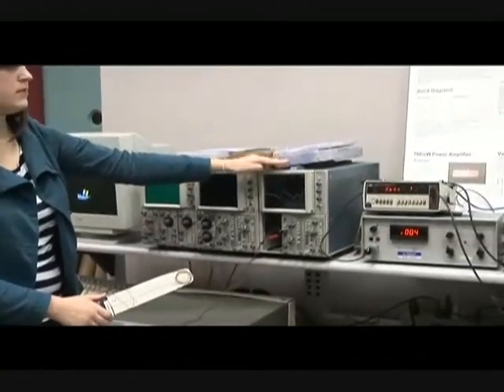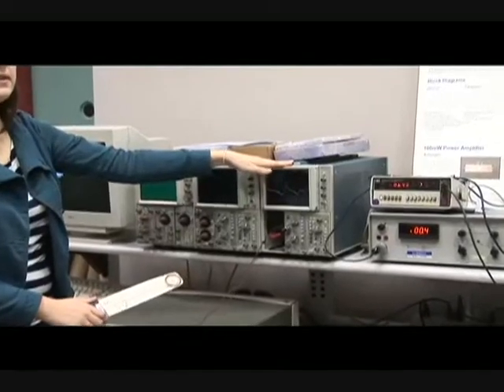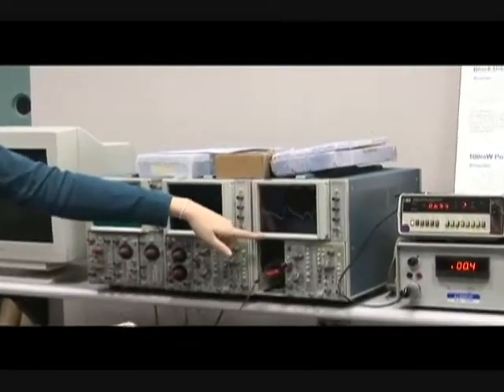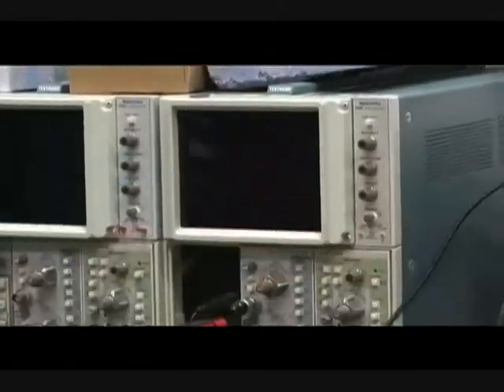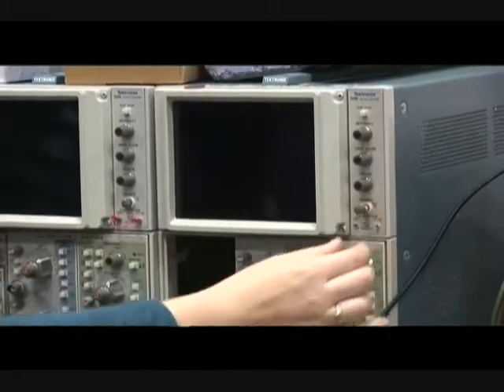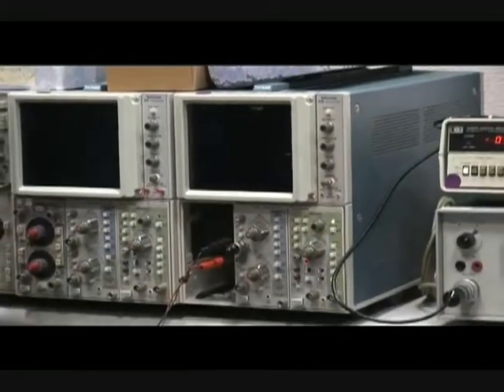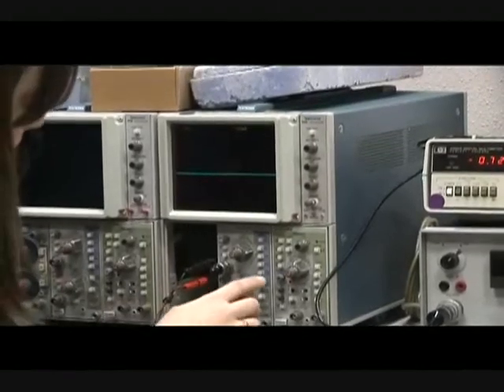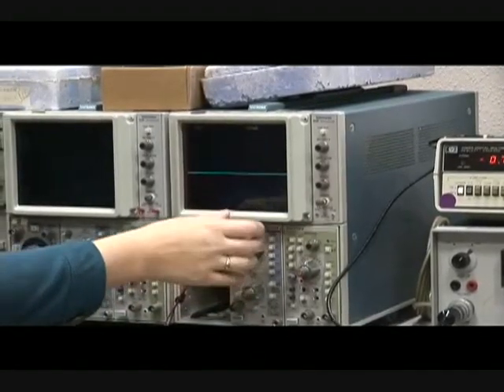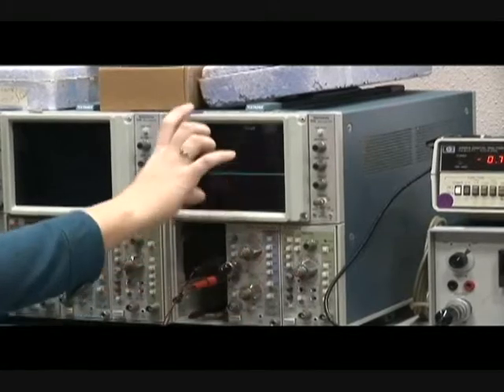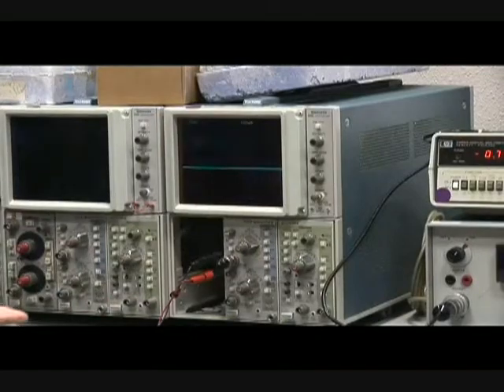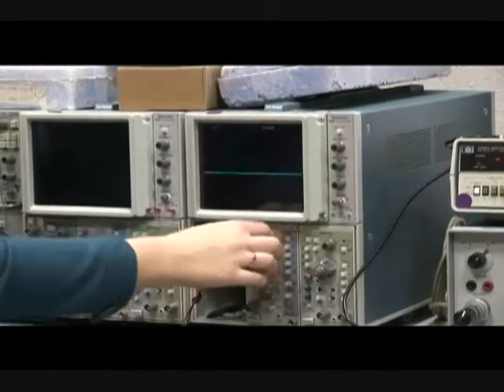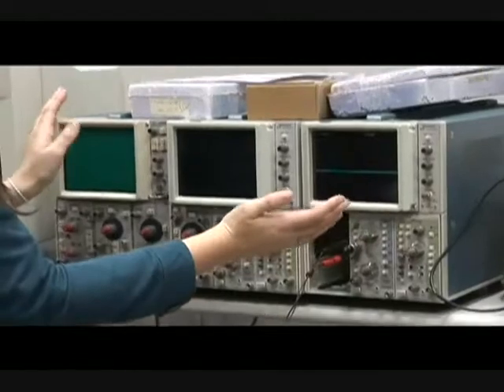And you will set up the storage oscilloscope so that it'll freeze once high voltage is triggered. So the way you turn this oscilloscope on, first of all, here's the power button. You just pull that out, and you want to make sure that your vertical axis is at a good scaling so that you can see the peak of your voltage. So you may need to adjust this to change the divisions.